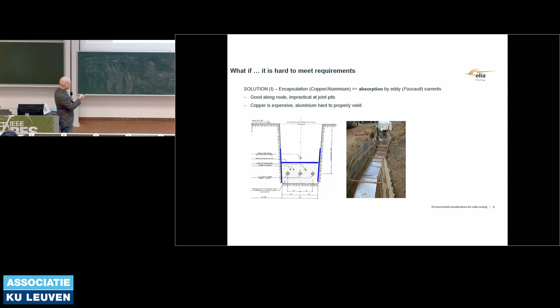We did this for a route of about 30 to 40 kilometers between two substations. Some rural people or farmers were really sensitive about this. You would see copper sheets, welded aluminium sheets, and welding and aluminium don't go well together. So these people really bought magnetic field meters, costing 5,000 to 6,000 euros, and almost every week they would pass by the cable route to measure if the system would work. At some point they found a crack, and wanted to have the cable shut down. We said, okay, thank you, you found a crack, we'll weld it again. This sounds like a fun fact, but this is really how people react to any of these high voltage installations.